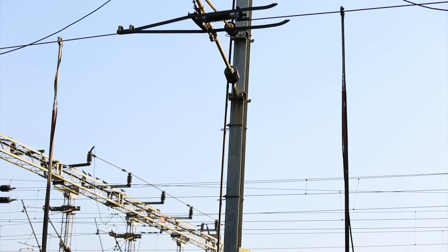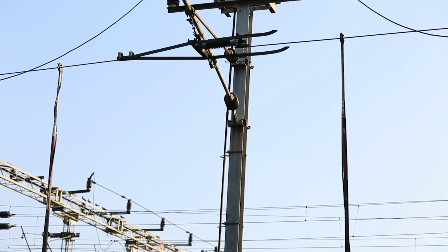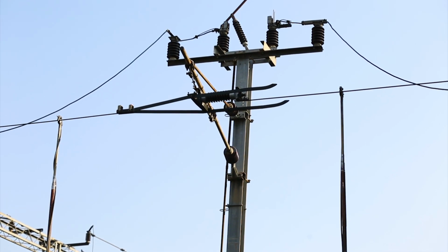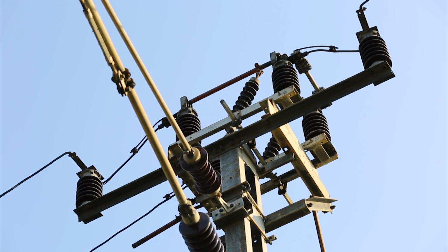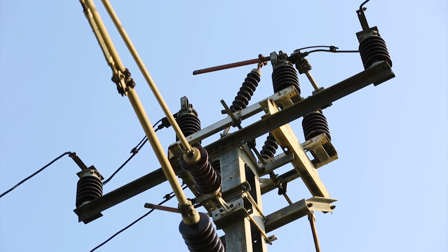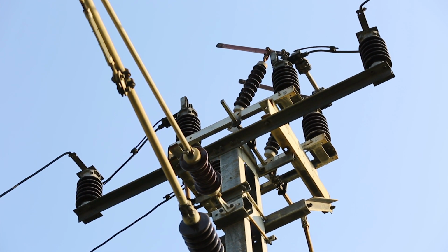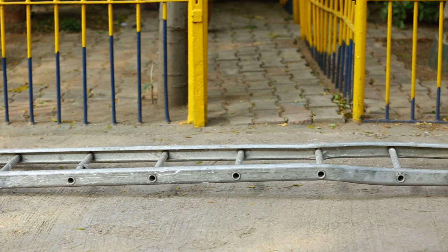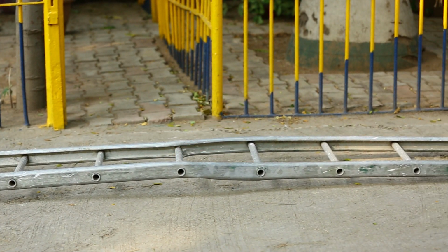When work is to be carried out on an isolator, both sides of the isolator should be earthed at 2 points. Even when earthing is provided by isolator switches with earthing heels, additional temporary earths shall also be provided both sides of the isolator at 2 points. Use of old ladder having less strength should be avoided.